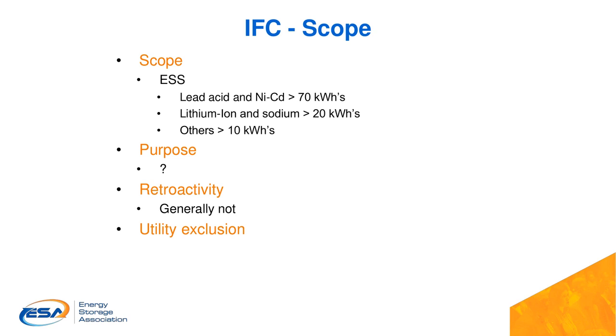Again, it's generally not retroactive. One pretty big difference is that the IFC has a utility exclusion in its scoping statement. It says that ESS installations under the exclusive control of utilities or their agents are excluded from the requisites of the standard or the code. And that's pretty significant for anybody doing grid-scale ESS.